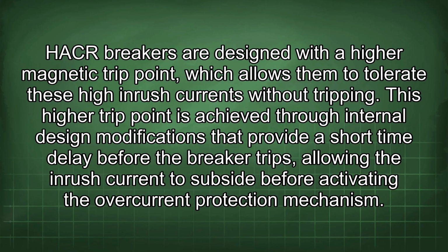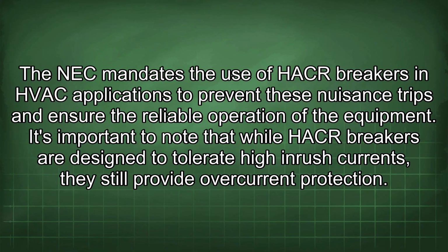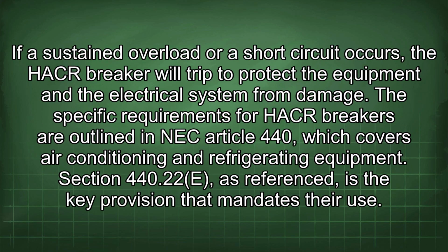HACR breakers are designed with a higher magnetic trip point, which allows them to tolerate these high inrush currents without tripping. This higher trip point is achieved through internal design modifications that provide a short time delay before the breaker trips, allowing the inrush current to subside before activating the overcurrent protection mechanism. The NEC mandates the use of HACR breakers in HVAC applications to prevent these nuisance trips and ensure the reliable operation of the equipment. It's important to note that while HACR breakers are designed to tolerate high inrush currents, they still provide overcurrent protection. If a sustained overload or a short circuit occurs, the HACR breaker will trip to protect the equipment and the electrical system from damage.